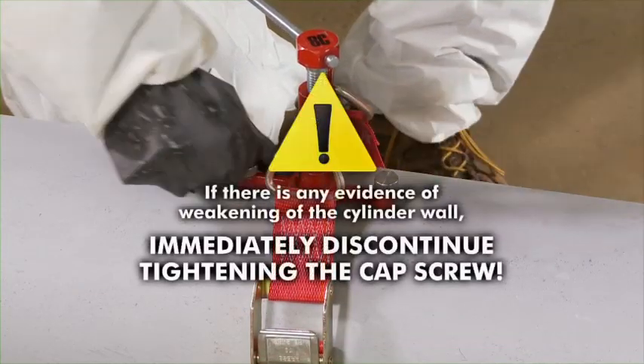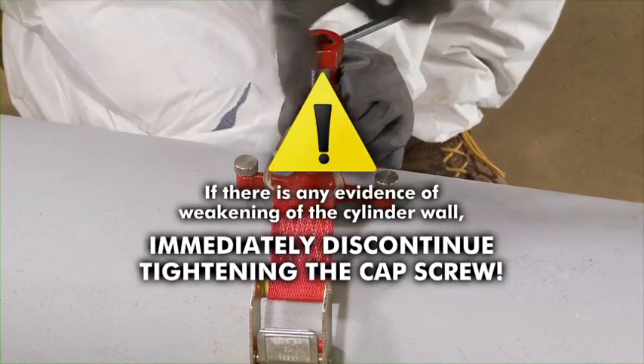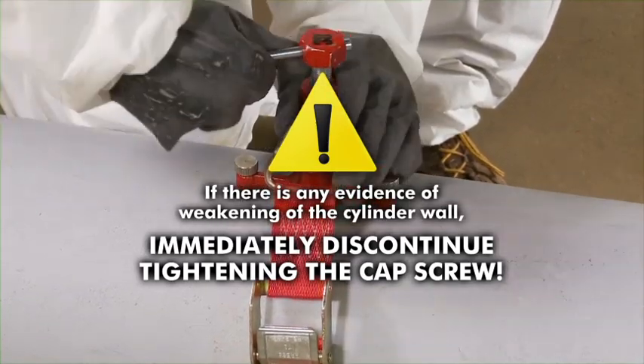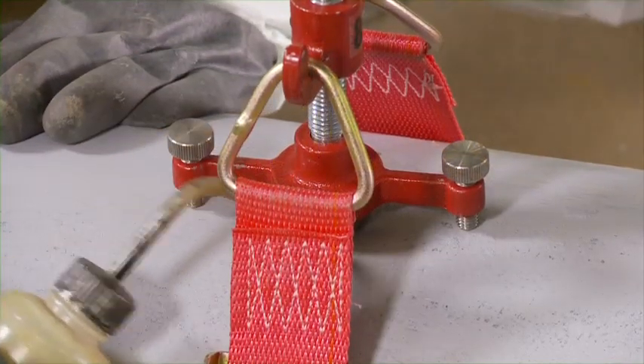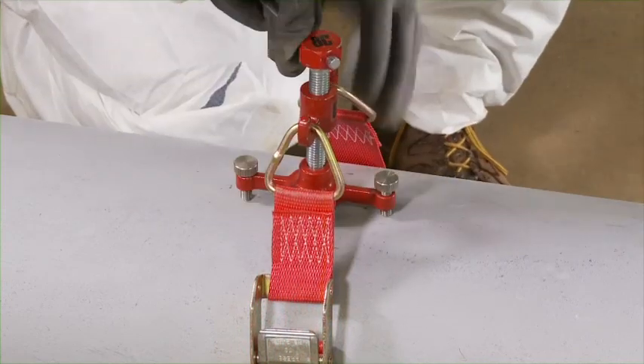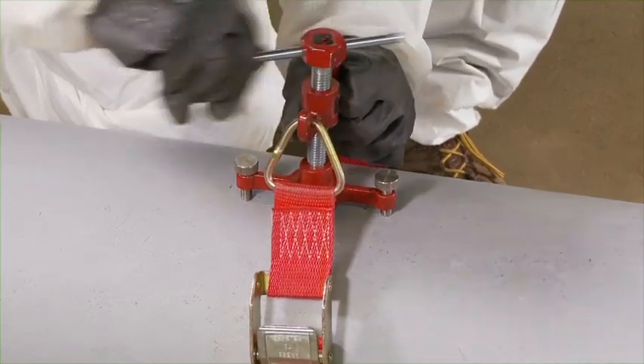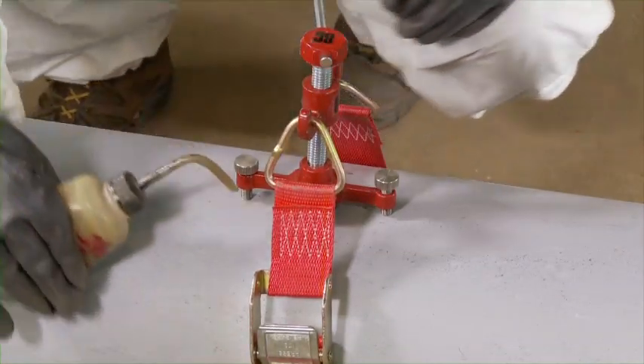Caution: if there is any evidence of weakening of the cylinder wall, immediately discontinue tightening the cap screw. Sealing pressure is supplied by the middle cap screw — this stops the leak. Adjust the thumb screws for stabilization only. Test for leaks. If the leak persists, further tighten the cap screw. Thumb screws can be adjusted independently to apply pressure on opposite sides of the gasket to stop the leak. Test for leaks.